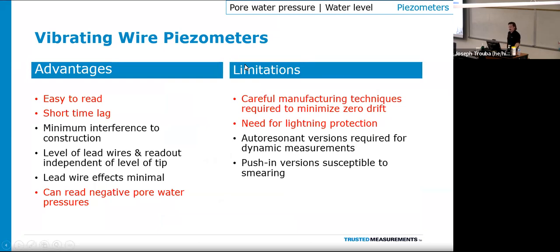So some advantages of using vibrating wire piezometers: they're very easy to read. It's a very short time lag, so you're getting efficient data quickly. They can read negative pore pressures, typically up to negative 15 psi. And then some limitations: it takes careful manufacturing techniques to minimize that zero drift over time. Those are very important. Companies around the world pride themselves on manufacturing these vibrating wires to the correct specifications, so you get good longevity out of your instruments over time, and obviously the correct accurate measurements. And then there is a need for lightning protection in some applications. As you mentioned, there's a built-in arrestor in all these instruments.